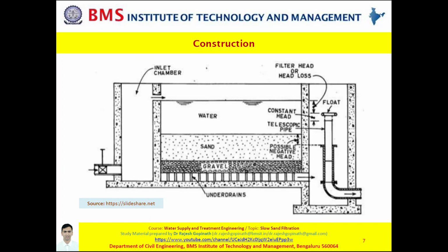If we are looking at a depth of 60 centimeters divided into 4 layers of 15 centimeters each, then in the first, topmost 15 centimeters, the gravel size will be 3 to 6 mm. Below that, 6 to 20 mm. The one below that, 20 to 40 mm. And eventually the bottommost layer will be 40 to 65 mm.